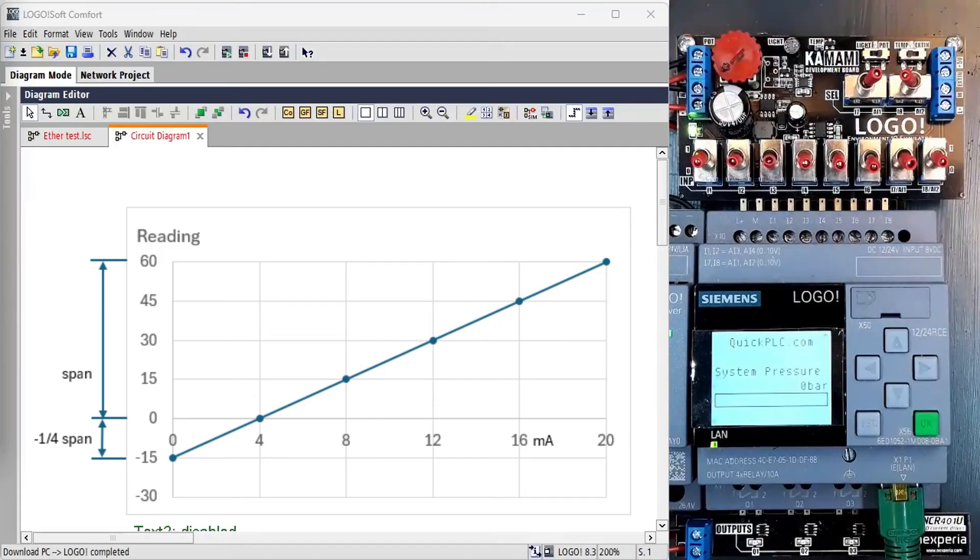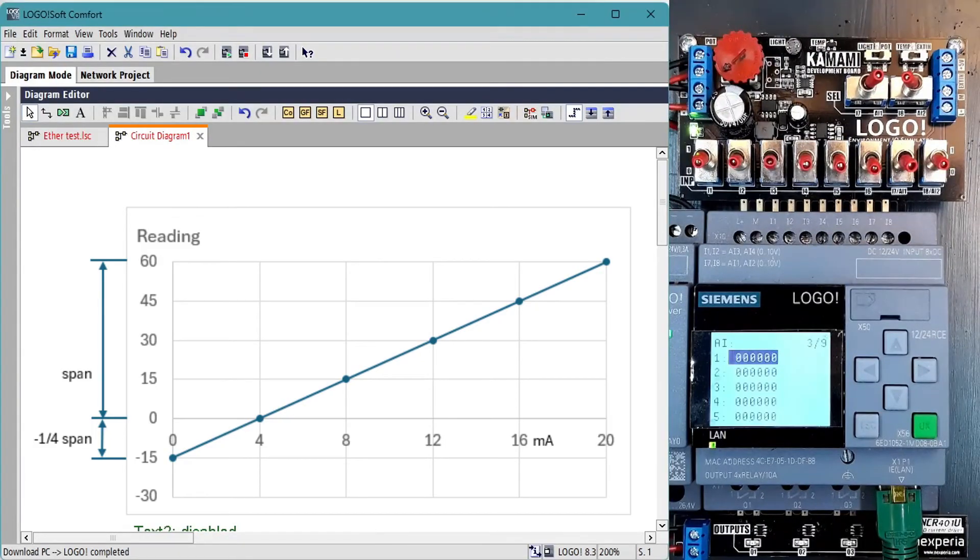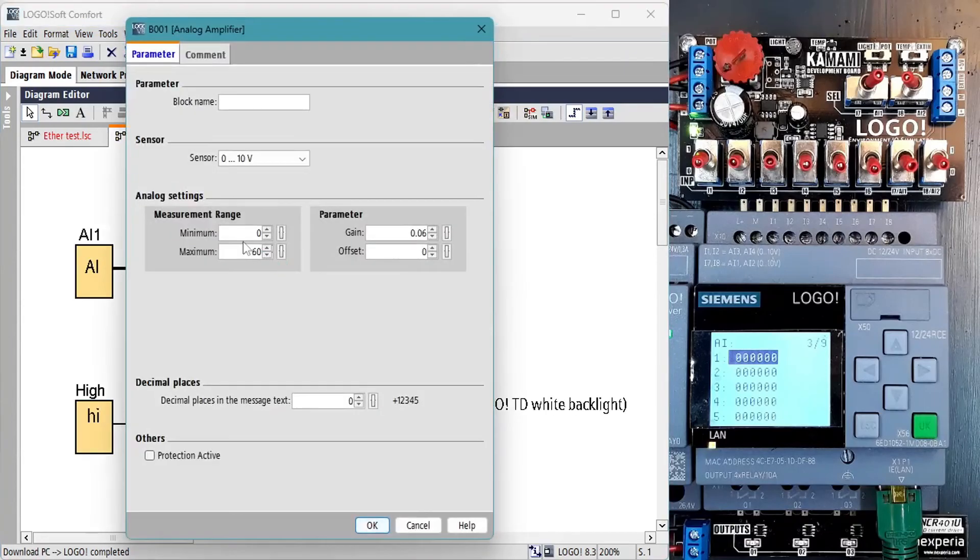When 4 milliamp indicates a reading of 0 then the offset is simply minus a quarter of the span. In this case the span is 0 to 60 so the offset is minus 15 bar. We program that into the analog amplifier, download and test.